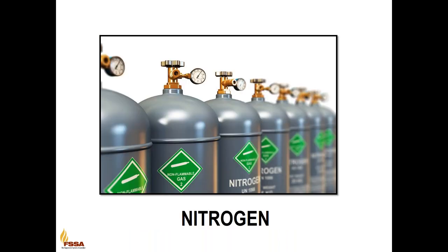Nitrogen fire suppression systems utilize pure nitrogen, which is also a naturally occurring gas. In typical fire extinguishing concentrations, it's safe for use in occupied spaces and it poses no threat to the environment. Nitrogen operates as a fire suppressor, reducing the oxygen content within a protected area to a point which will extinguish the fire without compromising the safety of the individuals present in the room. Nitrogen will not decompose or produce any byproducts when exposed to flame.